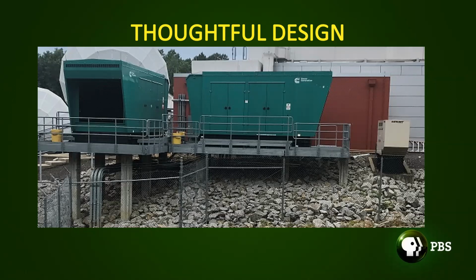One of the things that happens here is when we have an ice storm, the wind tends to blow the precipitation into the front of the generator, which is where the radiator is located, and the radiator freezes over. Then when the generator starts, you have kind of a race with no real winner: will the generator be able to melt the ice off its radiator before it overheats? Most of the time you lose. So in order to protect against that, we face the generators different directions. That's one of those thoughtful design things. We could have faced them any direction, but we tried to make sure that at least one of them should be facing away from the prevailing wind.